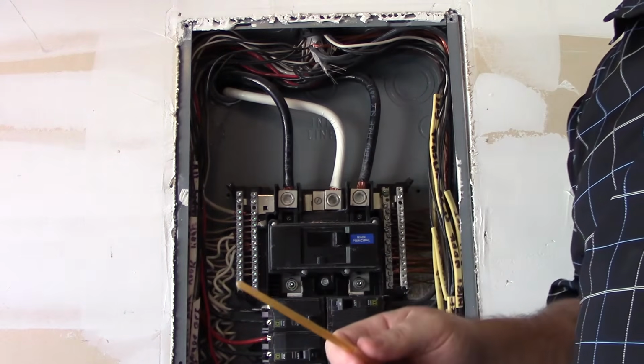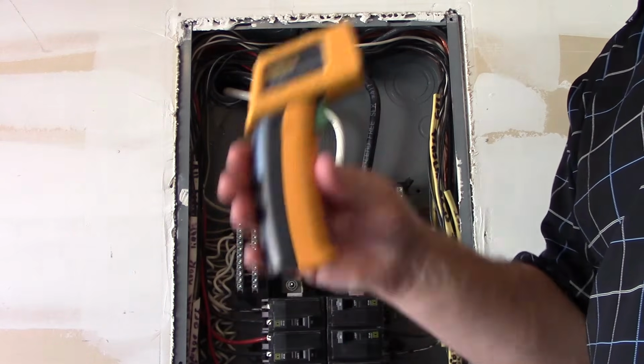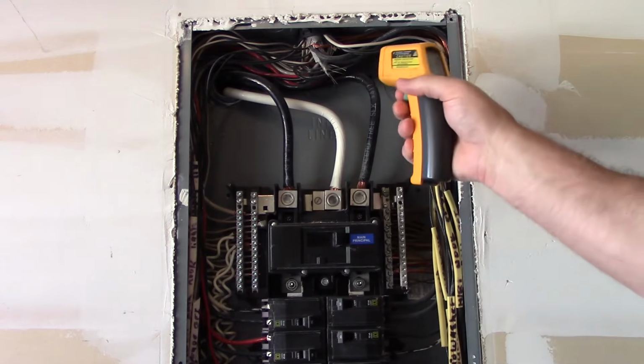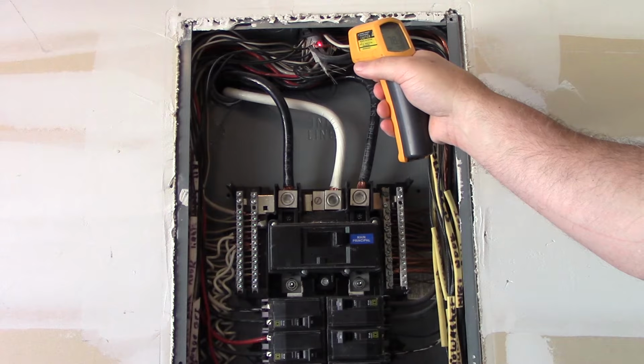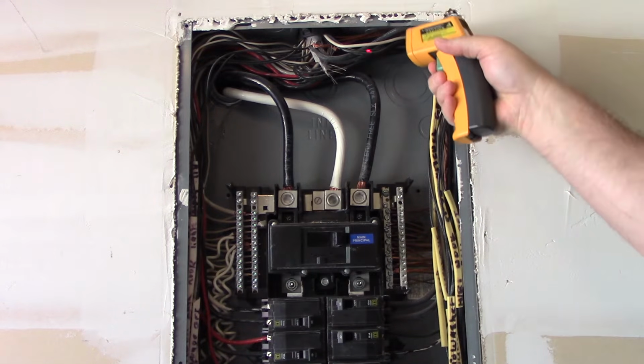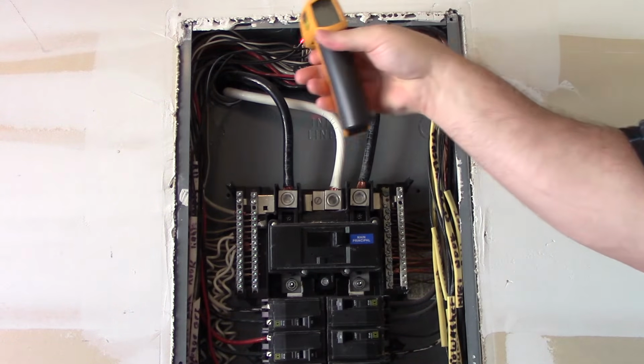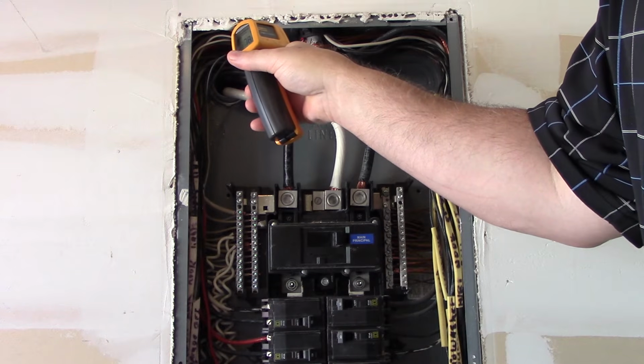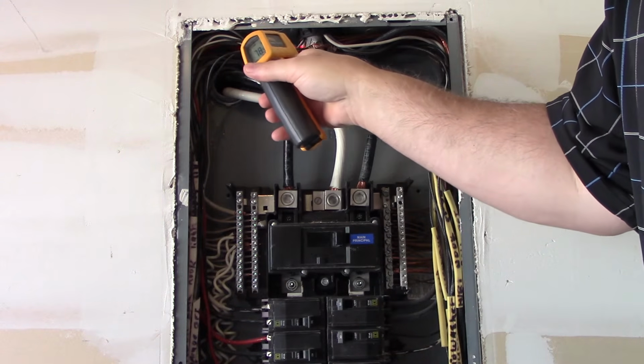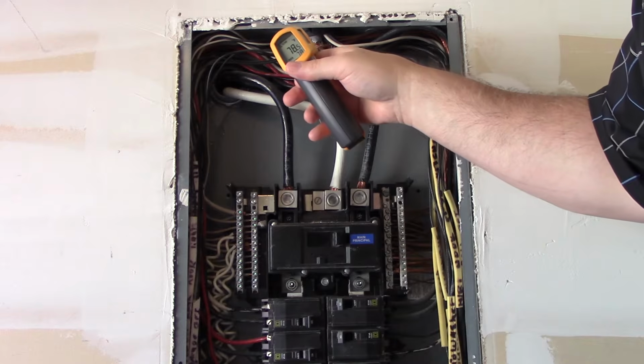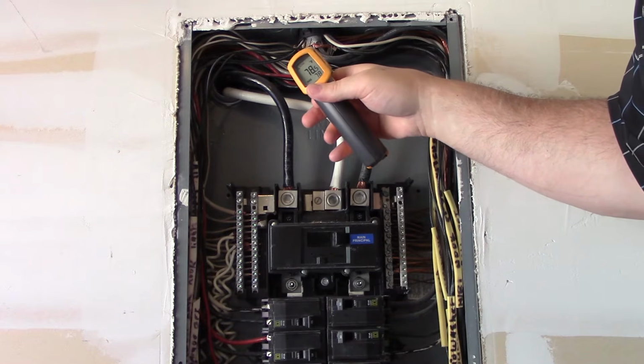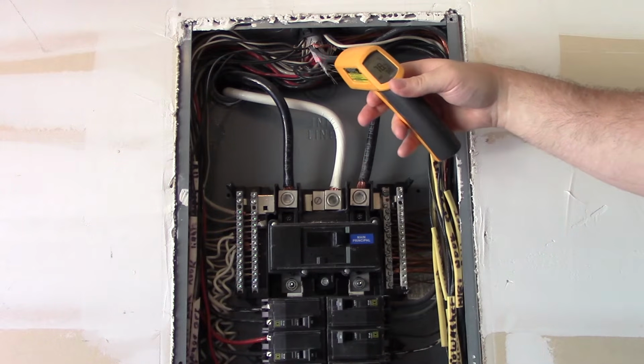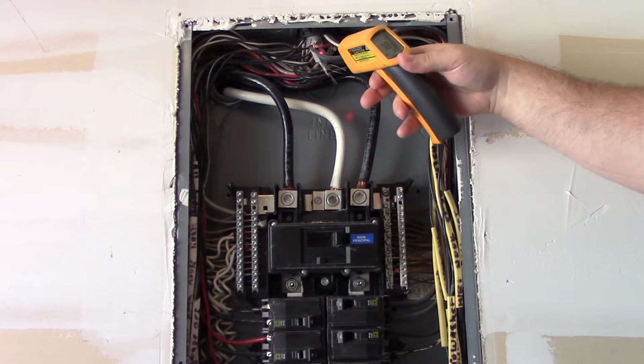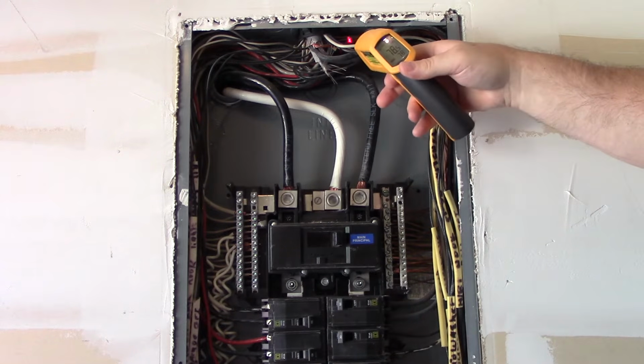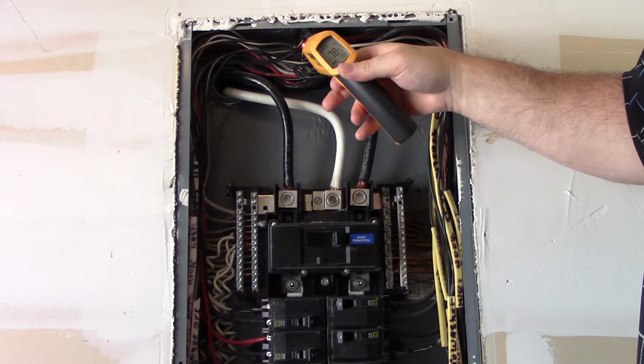So the one thing that we could do is take our infrared thermometers and shoot it in here at some of the cables, some of the conductors, and see if we get any evidence of elevated heat, just as a precaution. Look in here and then see around the cabinet, do we see anything? And here everything's about 78. And this is in the morning in Texas, so that's about right for about 10 o'clock in the morning here. Everything looks good. I don't see anything.